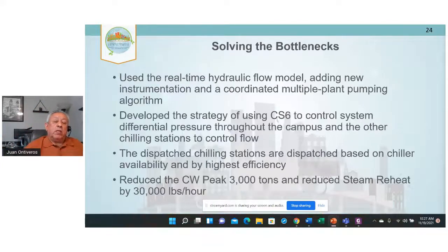So what we basically did is we used the model to say, okay, where are our bottlenecks? And what we learned is that chill station 6, which was in the middle, we wanted to use a lot because it was very, very efficient. It was the most efficient plant at the time. Remember I said it was a 15,000 ton plant, but I really could only do 12,500 because of the tower. So we'll take it up to 12,500. Once we reach that point, we start to lower it. And then we use the other stations to control flow. So this controls pressure, the other stations control flow.